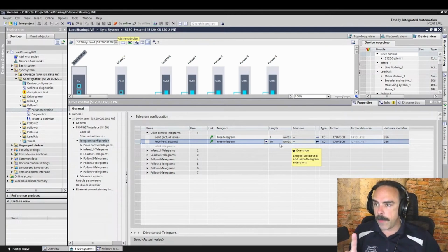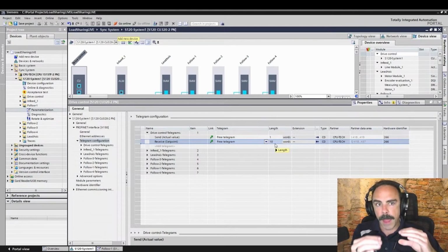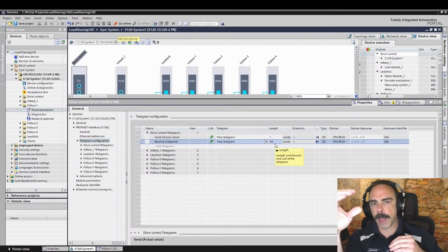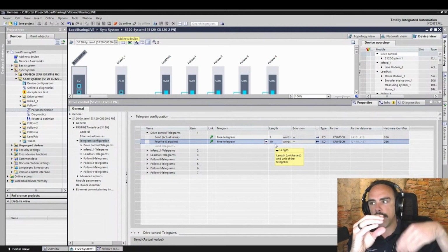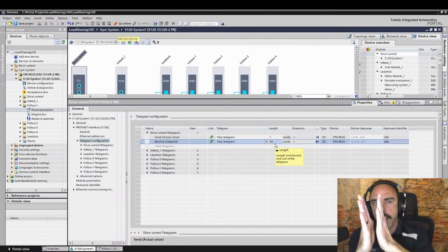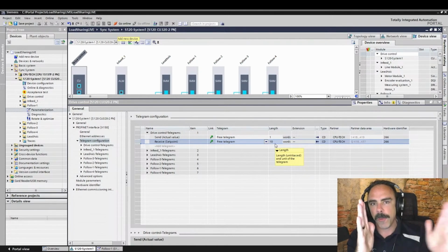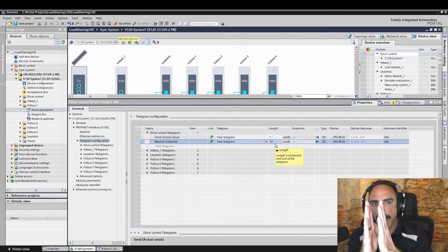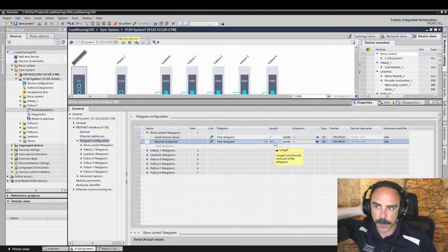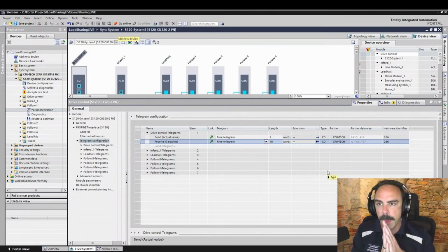And that's pretty valuable information there. I put in the control unit first, so it allocates one word, and so it was at the beginning. Then I brought in the infeed, and so it's going to butt all of those up together. And well, it didn't have enough space because when it put the infeed in, it only allocated enough space for one word instead of 10 words. And that's what went on there. So that's why I had to move this partner area over to a new address space so that it has more output, or I guess more input, I should say.